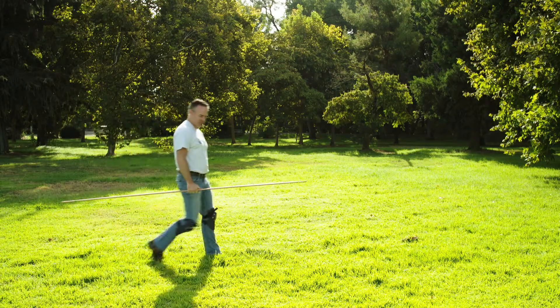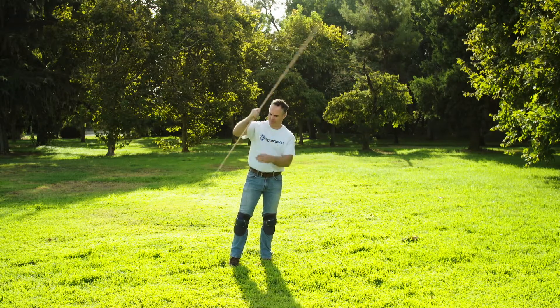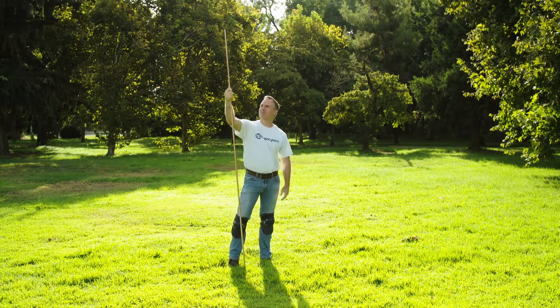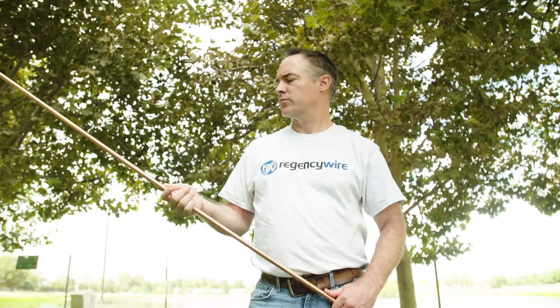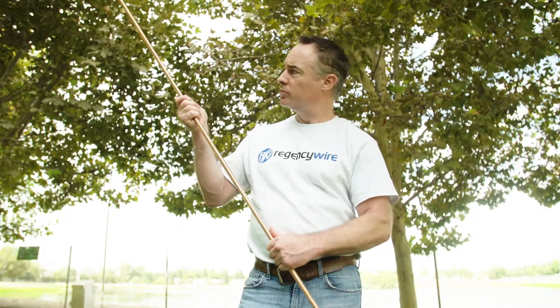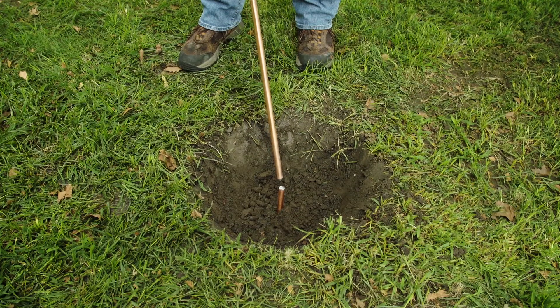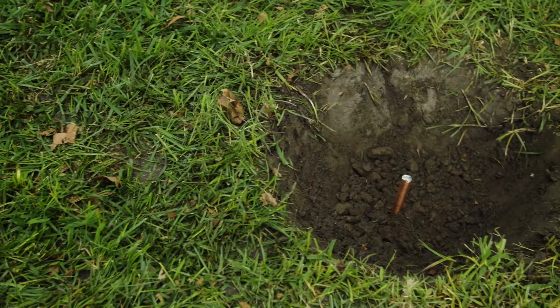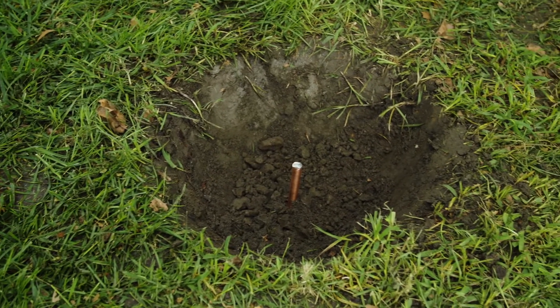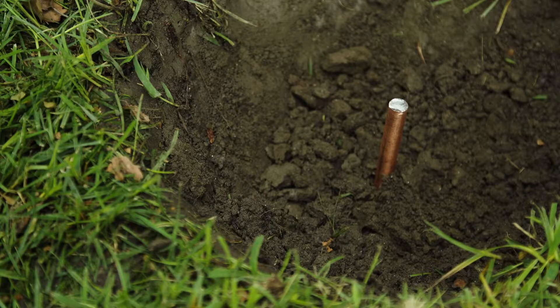Ground rods are the most familiar method of grounding. These are 5/8 inch in diameter and typically 8 feet, 10 feet, or 12 feet long. Ground rods are driven into the soil to produce good contact. A fully buried 10-foot ground rod will have about 230 square inches of soil contact. The more soil contact, the lower the impedance of the grounding circuit, which attracts the surge and protects the system.